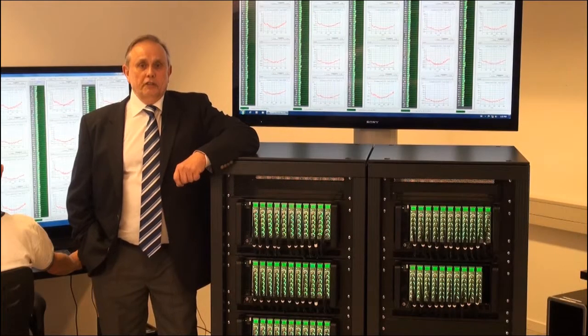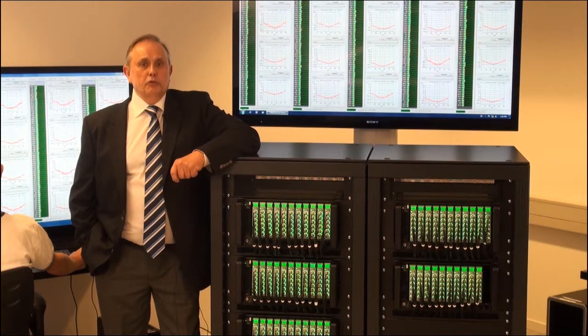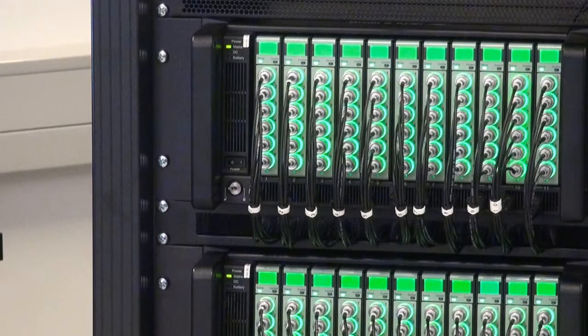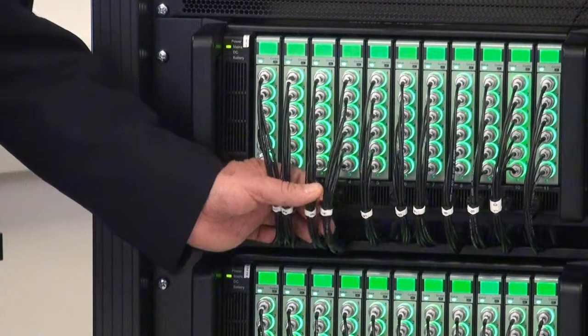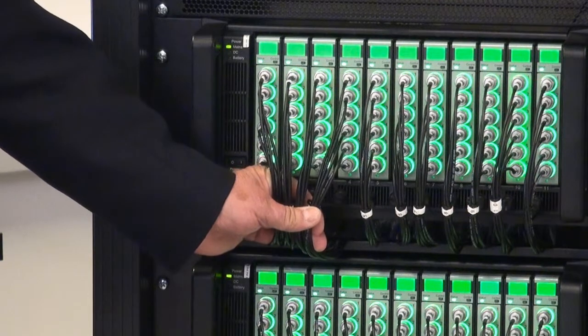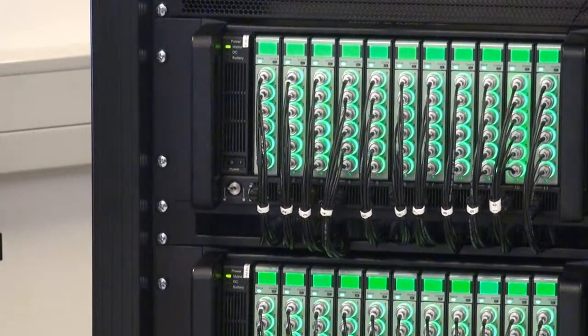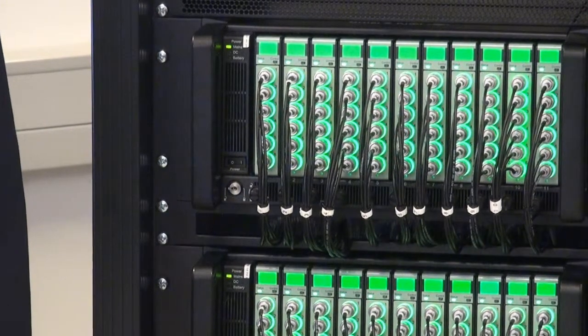This gives two distinct advantages. Considerable setting up time is saved between individual tests, and only very short analogue cabling from satellite to data acquisition system is needed. Short cabling increases the quality of the measured signals and decreases the risk of cable integrity failure — important in a system with 320 channels to keep track of.